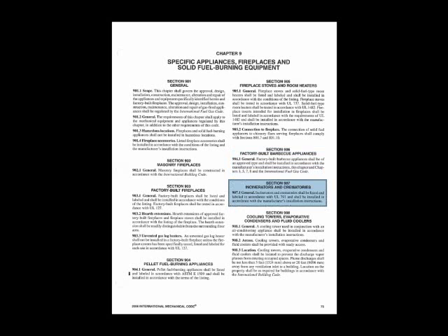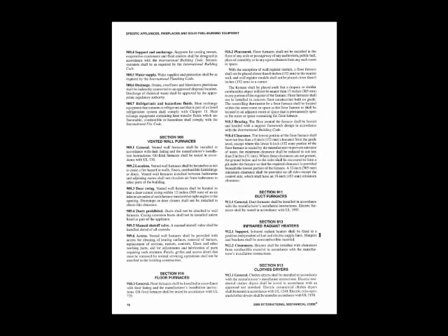Section 908 talks about cooling towers, evaporative condensers, and fluid coolers. Talks about how they have to be vented, their access, and the locations thereof. They have to address the support, the anchoring, the water supplies. Section 909 talks about vented wall appliances. Okay, this is any appliance you mount on the wall, like little gas heaters. 910 talks about floor furnaces, how they're installed, the placement of them, and where they're at.